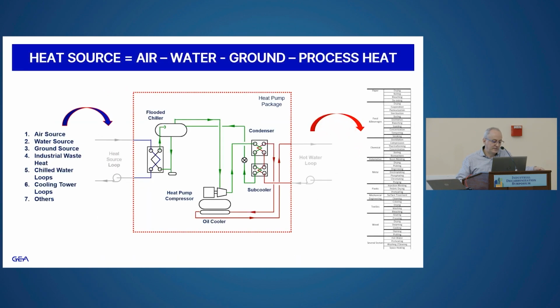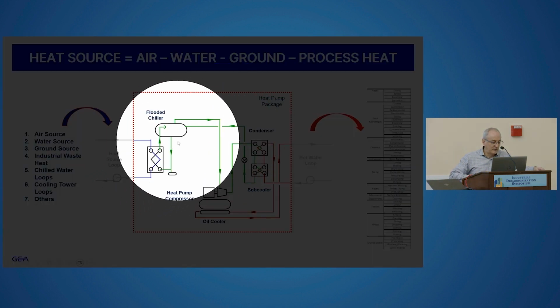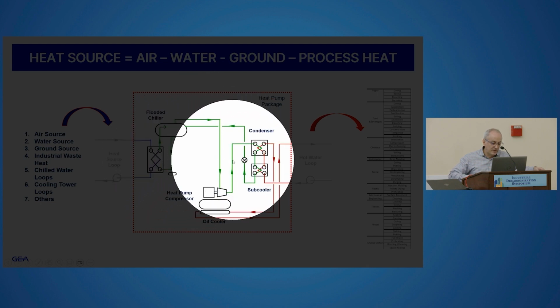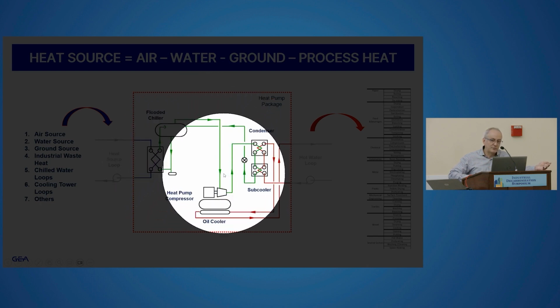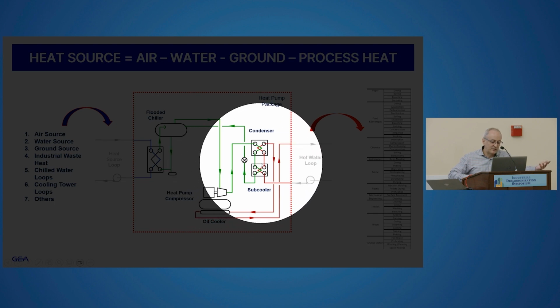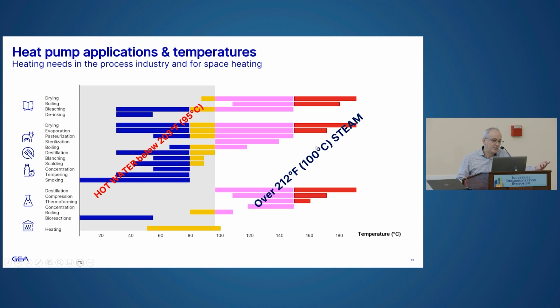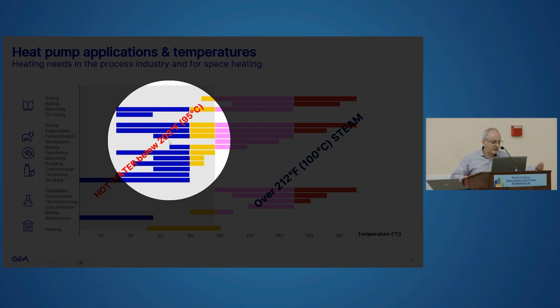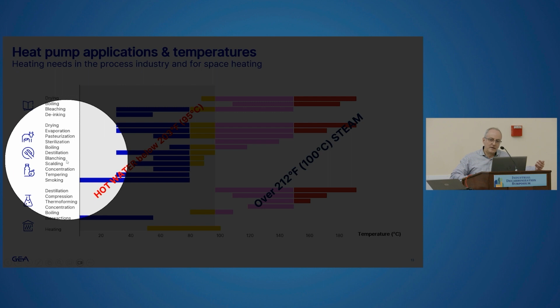So what happens is that you have different sources. You can use air source. You can have water, like river, ocean, lake, anything, ground. Geothermal loops are happening a lot. Any waste heat coming from a process, you get it into an evaporator, and it starts a refrigeration cycle inside the heat pump. We call it refrigeration cycle because it's still a compression cycle. And then that heat goes to a heat sink, and that's where you start making hot water or something like that. Depending on the temperatures and process, you have different temperatures. But with current technology available, and depending on refrigerants, you can get today up to 95 Celsius water leaving the heat pump, or 203 F. You can go into different processes like cleaning in place, pasteurization, blanching, evaporation, drying, things like that.